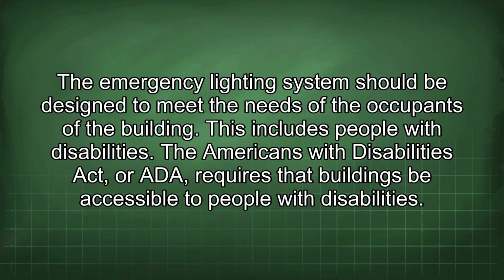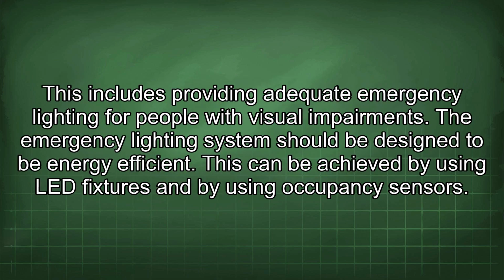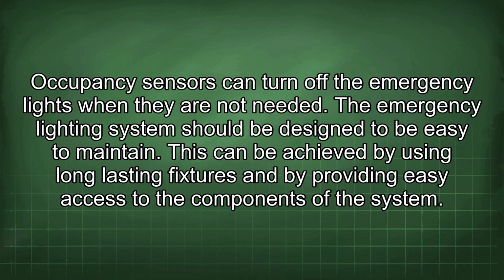The emergency lighting system should be designed to meet the needs of the occupants of the building. This includes people with disabilities. The Americans with Disabilities Act, or ADA, requires that buildings be accessible to people with disabilities. This includes providing adequate emergency lighting for people with visual impairments. The emergency lighting system should be designed to be energy efficient. This can be achieved by using LED fixtures and by using occupancy sensors. Occupancy sensors can turn off the emergency lights when they are not needed.